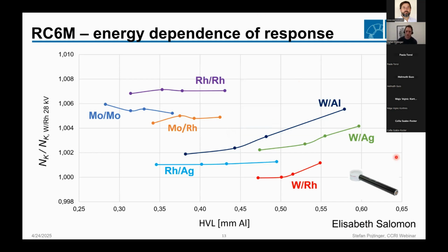This is also a good secondary standard ionization chamber that you can use for mammography, the RC6M ionization chamber. And here you can really see that for different anode filter combinations, you have different calibration coefficients. You can also see that it's a good introduction to have tungsten rhodium, because here you are really on the other side of the spectrum, so to say, compared to moly-moly. Moly-moly is currently the only standardized combination in the IEC standard. Again, overall, you can see that the ionization chamber generally has a relatively flat energy dependence in that range. Everything here is between 0 and 1% deviations between the calibration coefficients for that ionization chamber.